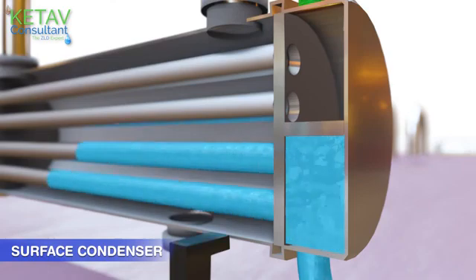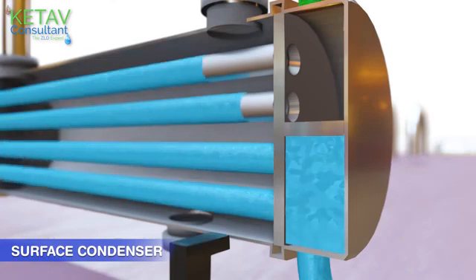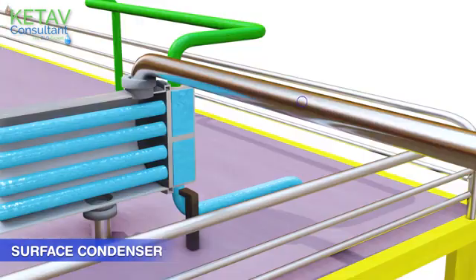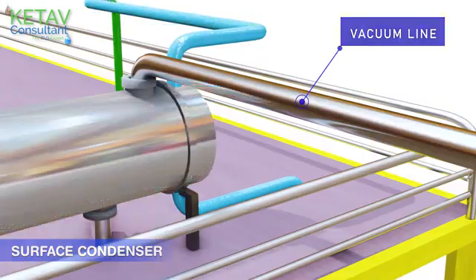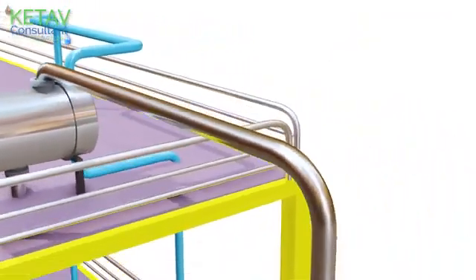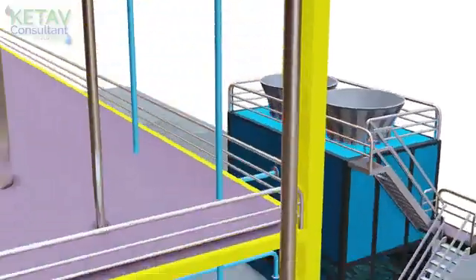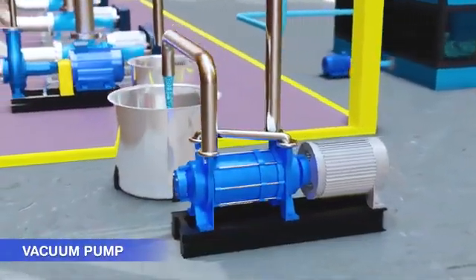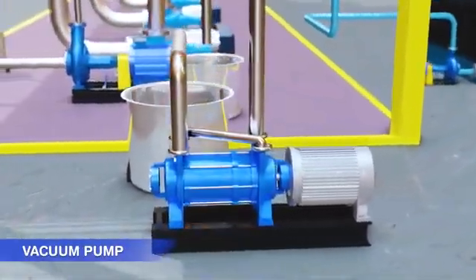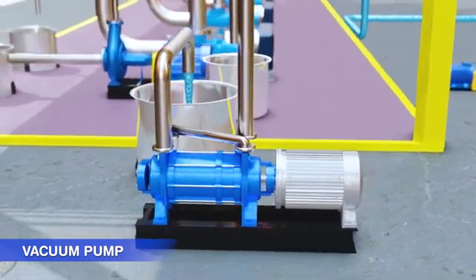Prior to beginning of the evaporation process, first cooling water circulation is started, and the generation of an appropriate vacuum is being maintained by the vacuum pump. The purpose of generating the vacuum is to lower the boiling point of water.